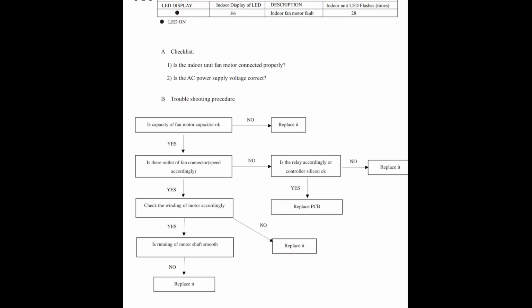So what's the checklist? Well, first, is the indoor unit fan motor connected properly? I checked, it is connected properly. Is the AC power supply voltage correct? Yes, it is. My unit has 240 volts AC, and that's what it's rated for. So our troubleshooting procedure is very simple. Is the capacity of the fan motor capacitor okay? Yes, it is. So I move on down.